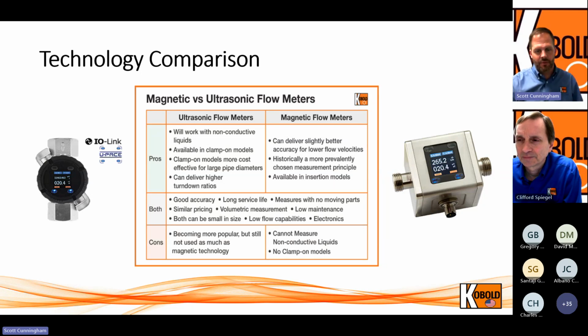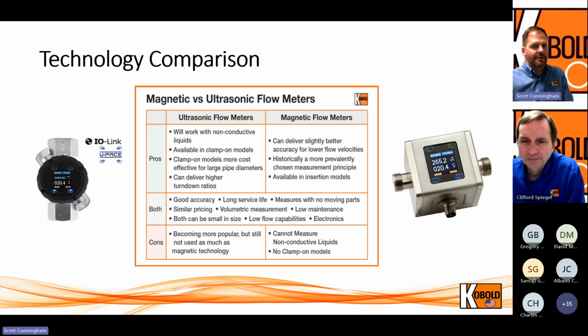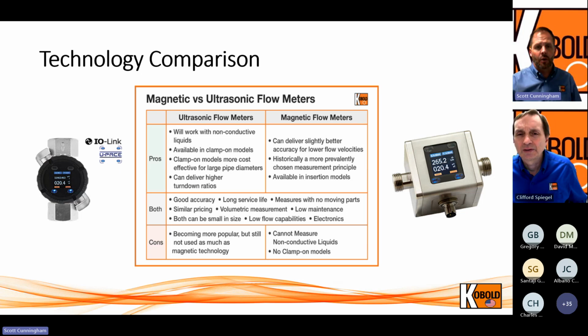You also have the added benefit of being able to use clamp-on ultrasonic, so you don't have to break into a pipe. You don't have to do any plumbing or line break-ins. And when you get into really large pipe diameters, sometimes a clamp-on technology is more cost-effective than trying to find an inline solution using maybe mag technology. You have extremely high turndown ratios, like we said, 250 to 1. So some of the downside to ultrasonic, it's still not used as much as magnetic inductive technology. It's not quite as popular, and it's a little bit more expensive for the inline solutions, or even the clamp-on, versus some of the magnetic inductive equivalents by line size.